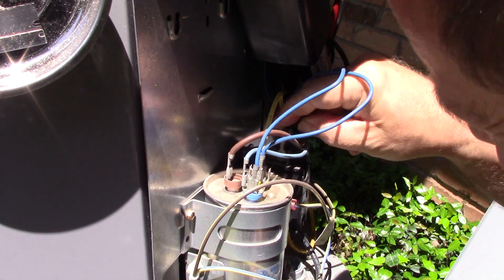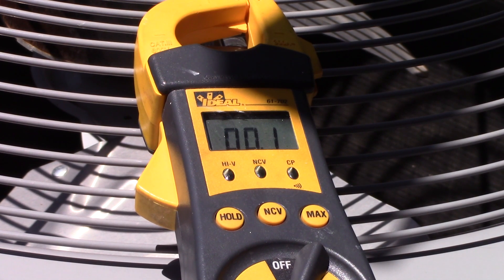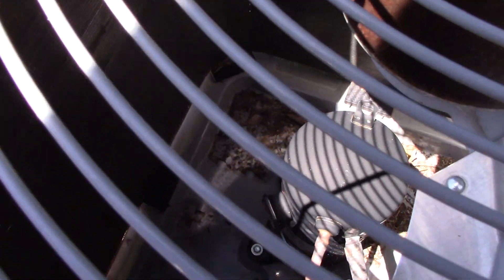It looks like everything is pushed on pretty well. I don't see any wires rubbing anywhere. Let's go ahead and check the capacitor while I'm in here. It shows to be 189 to 277 microfarads, so that one is actually reading a little bit low. But we'll just pretend we didn't see that. I took a brush and just gave that a quick brush out — all the loose debris and cobwebs and stuff like that.